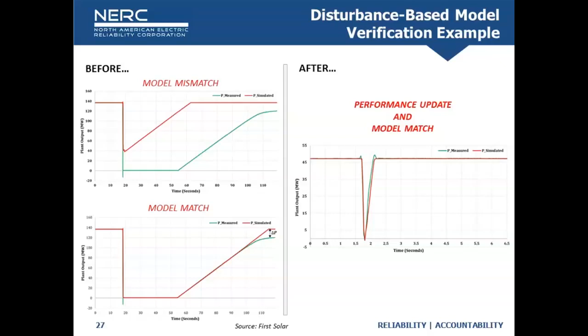We've seen a number of these success stories across all interconnections, which is great. So we put out an alert. We've had a couple of disturbances—the Blue Cut fire in August 2016 and the Canyon 2 fire in October 2017—and we're just getting ready to issue another disturbance report for the April and May 2018 disturbances, which looked very similar to Canyon 2. After Canyon 2, we issued an alert seeking data on momentary cessation settings and transient overvoltage settings, to identify the extent of the condition out there and recommend mitigating actions to support BPS reliability.